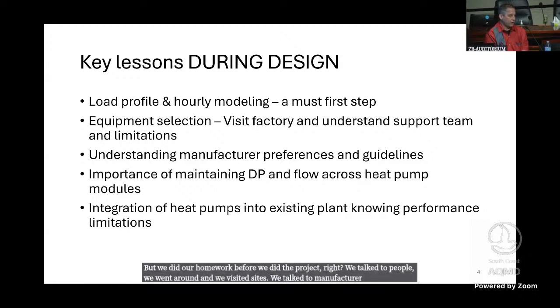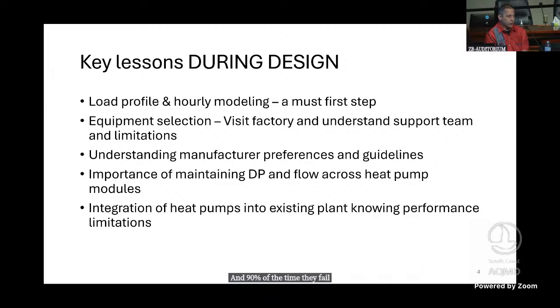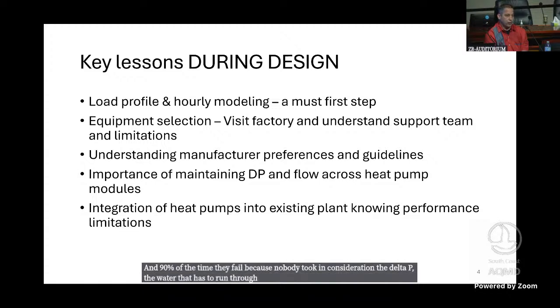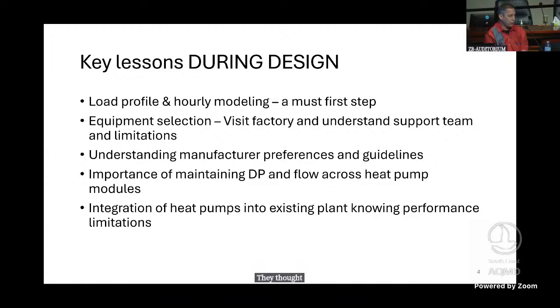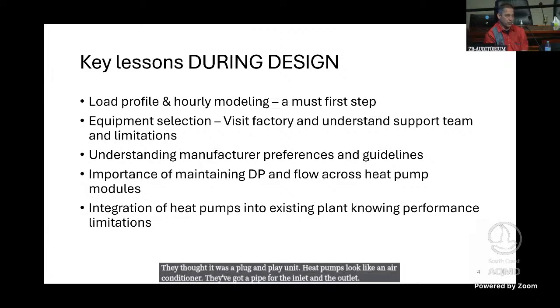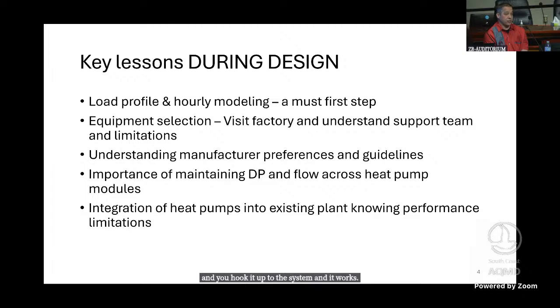Okay, why did they fail? 90% of the time they failed because nobody took into consideration the delta P and the flow of water. They thought it was a plug and play unit. Heat pumps look like an air conditioner, they've got a pipe for the inlet and outlet, you hook it up to the system and it works. And it doesn't, right? Because there are some nuances you have to understand. So doing that homework was the crucial first step.